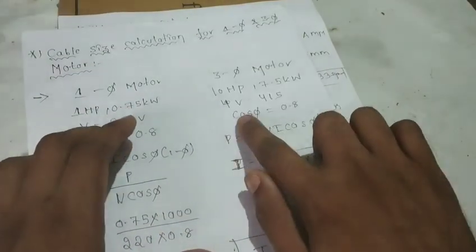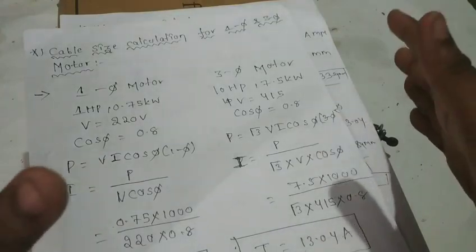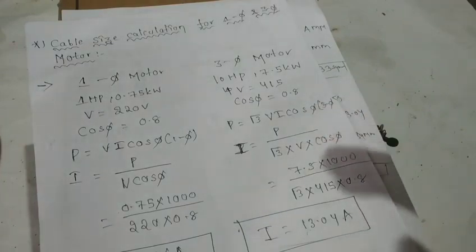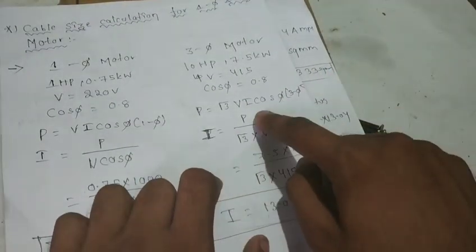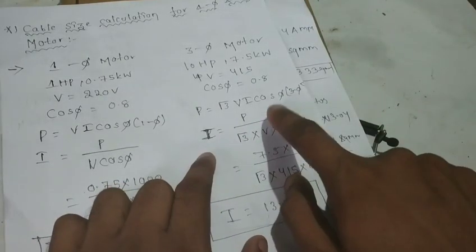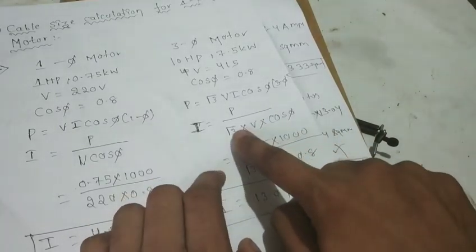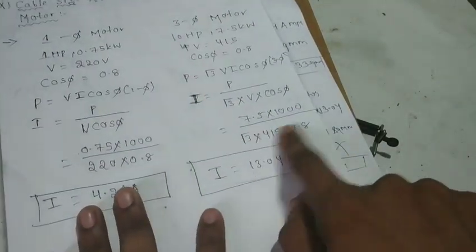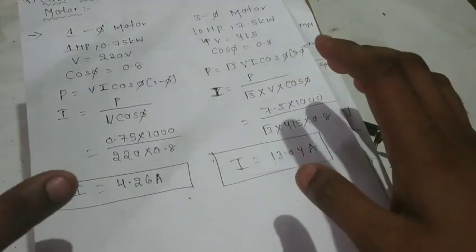This is the motor rated full load current. Using the formula I = P / (V·cosφ), now for the 3-phase motor: I = P / (√3·V·cosφ). Power is 7.5kW. So: 7.5 into 1000, divided by √3 into 415V, cosφ is 0.8. Final value: I = 13.04 amps. This is I1 for the 3-phase motor.